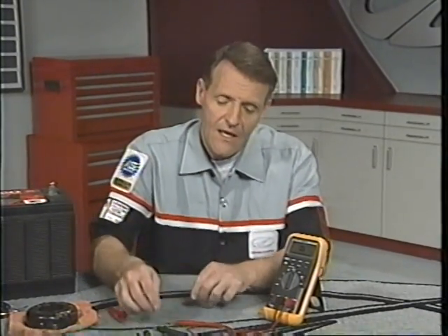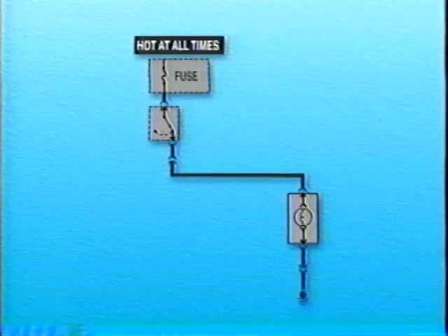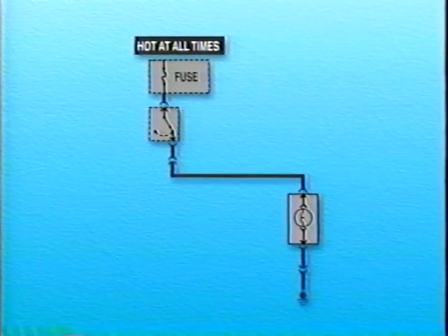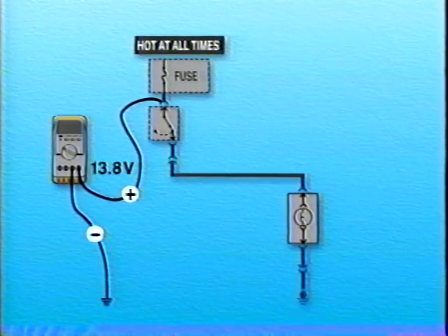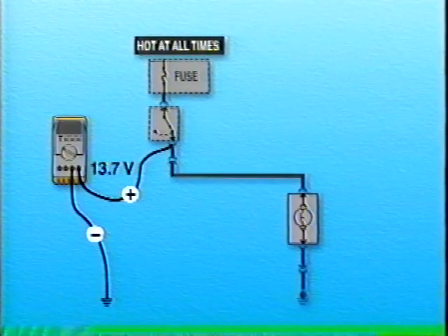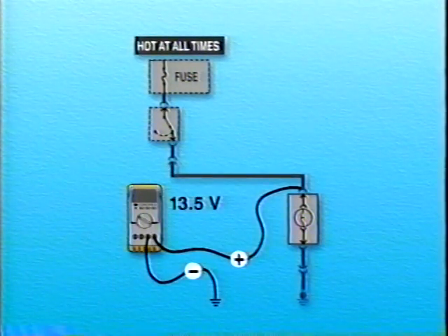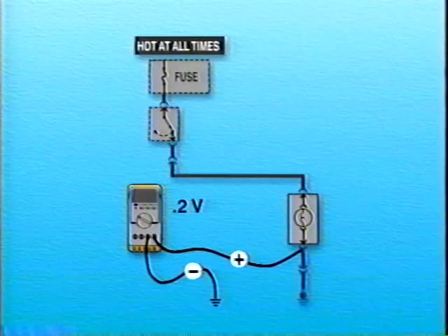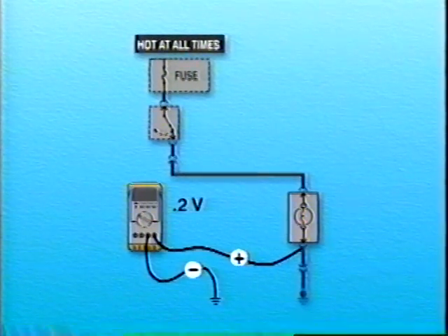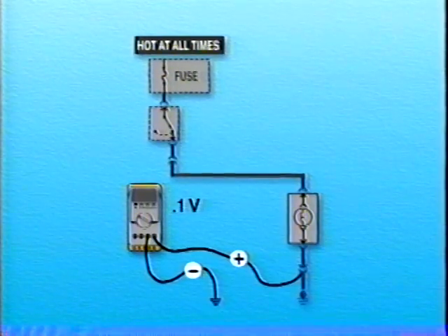We've reviewed the meter's basic functions. Before we move on, I want to make a pitch for using voltage drop, your biggest help in many tough diagnostic situations. To understand voltage drop, remember that all a voltmeter ever does is compare electromotive force, or volts, at one point with electromotive force at another. If an activated circuit is good, with little unintended resistance, then the difference in voltage between ground and each connection on the power side should be nearly the same as the input voltage. And the difference in voltage between ground and each connection in the ground section of the circuit should be close to 0 volts.